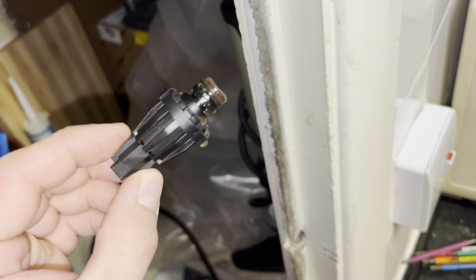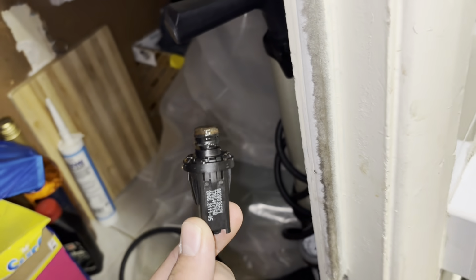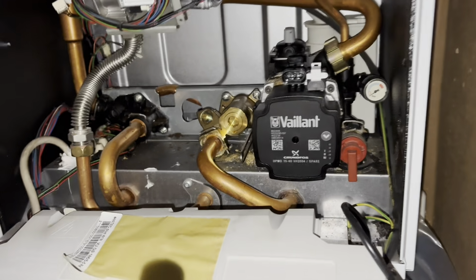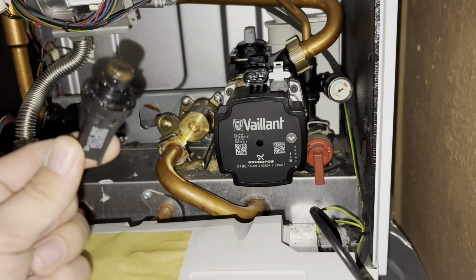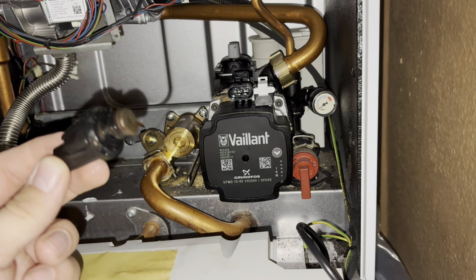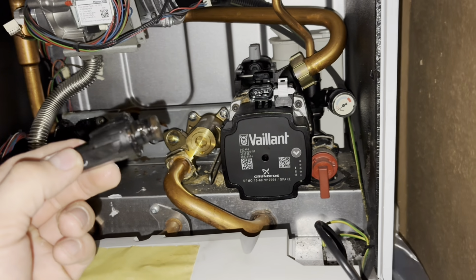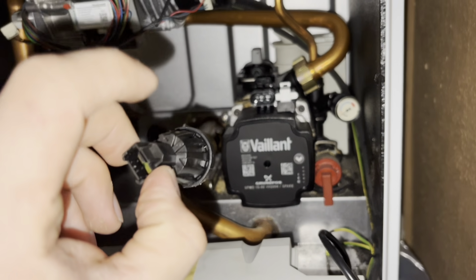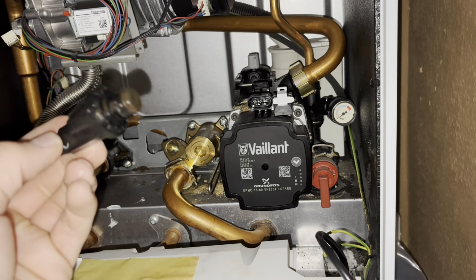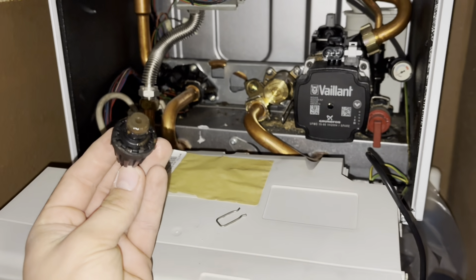So when you have an F75 on a Vaillant, it tends to be usually the water pressure sensor or the pump. It's pretty easy to tell. If your boiler comes on and the pump is running and you still get an F75, it usually means it's the water pressure sensor because it doesn't pick up the 0.2 movement on the pressure when the pump kicks in, which would cause a F75 lockout.